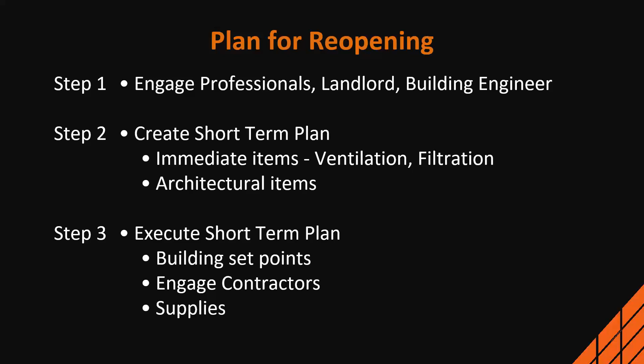If you just dropped in the MERV 13 filters and your system couldn't handle it, you're basically going to drop the ventilation way down because your air can't get distributed properly. So that becomes its own problem. You've got to be careful with that kind of stuff.